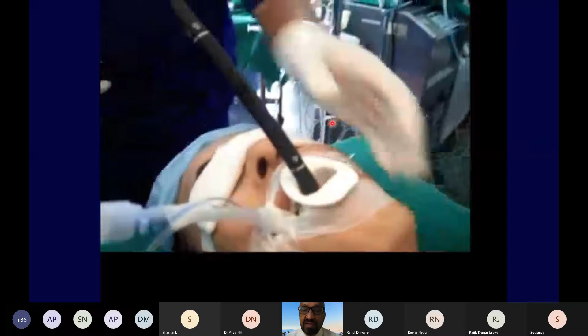Then coming to the standard words which are used, if the probe is pushed into the esophagus, it is called advance, and if you are pulling it out, it is withdrawal. The probe can be anteflexed, which means it is bent forwards, or retroflexed, which means it is bent backwards, by using the big knob on the control of the probe. And we can change the multiplane angle from 0 to 180 degrees, which is called rotate forwards if you are increasing the angle from 0 to 180, or if you are decreasing the angle from 180 to 0, it is called rotate backwards. The probe also can be flexed right or left by using a small wheel on the knob, and this is called flex to the right and flex to the left.